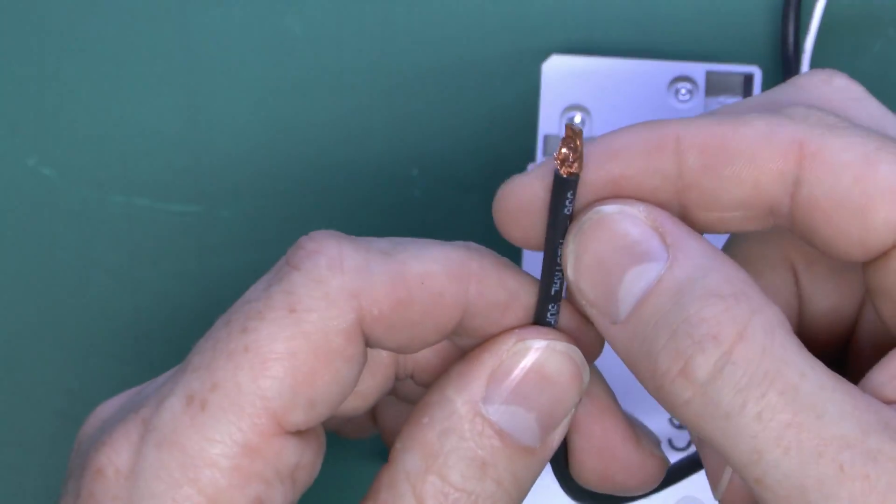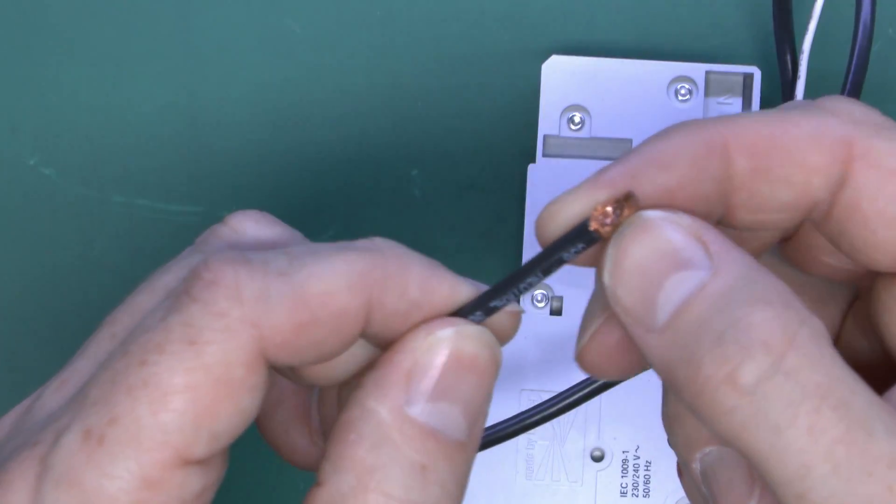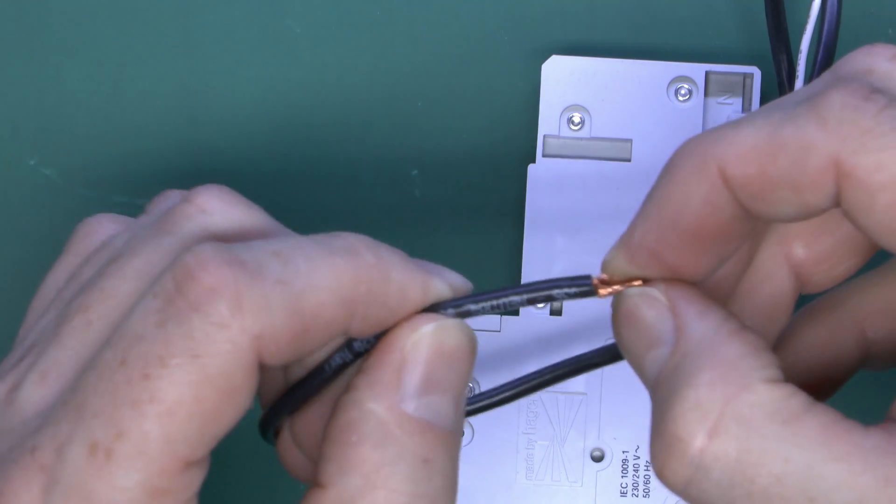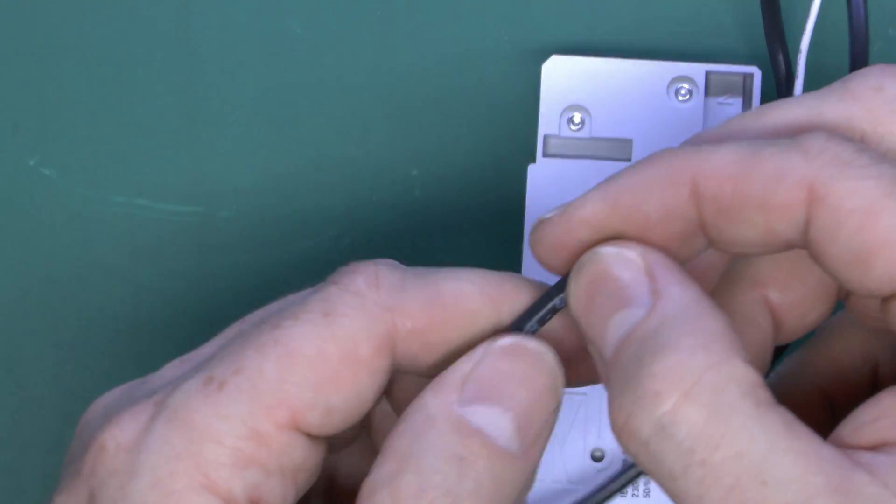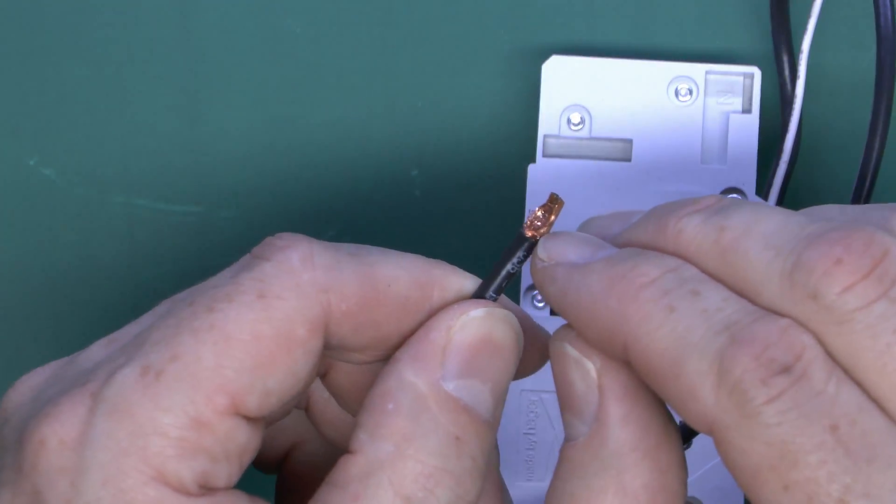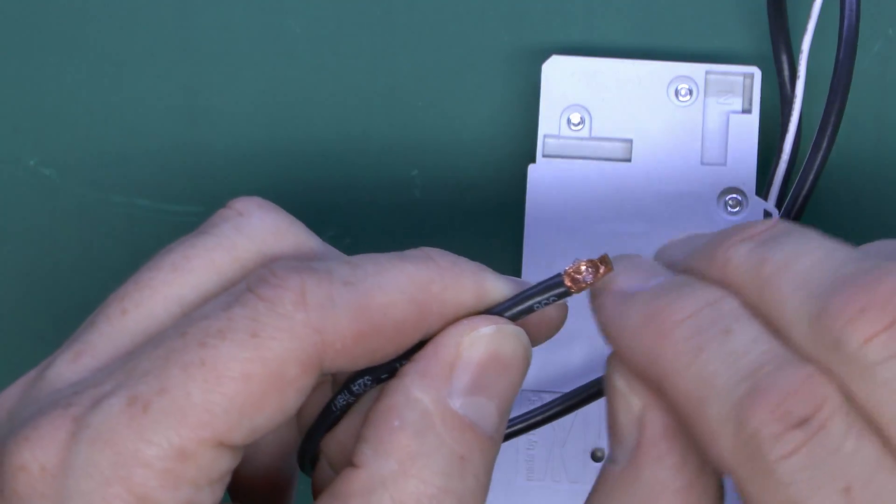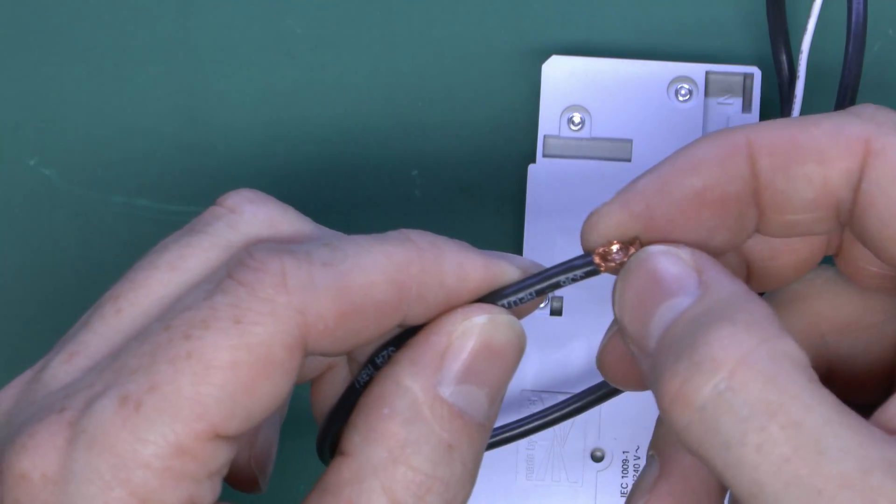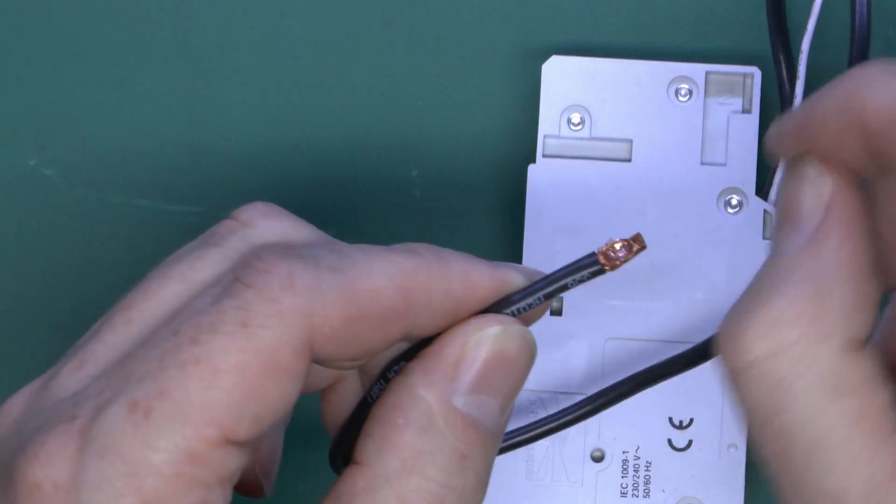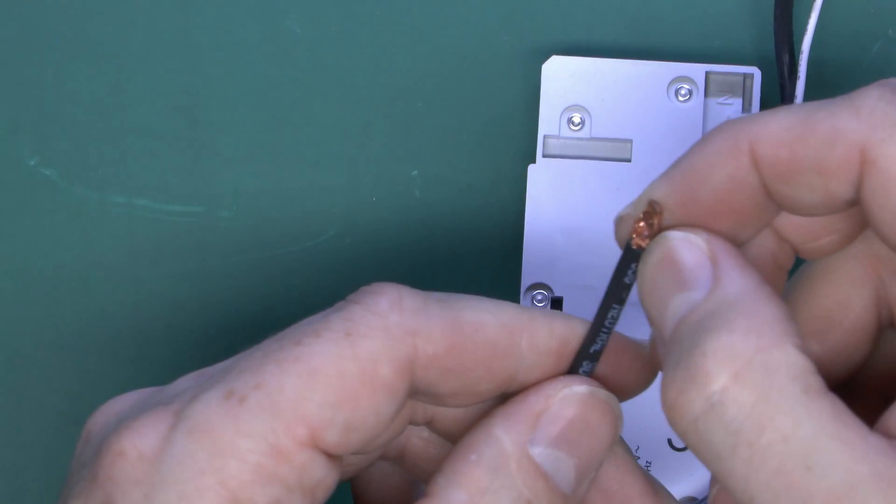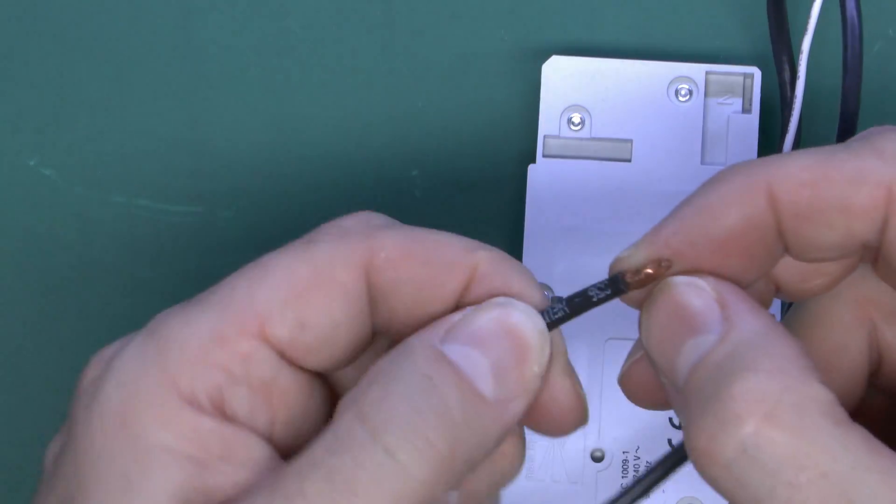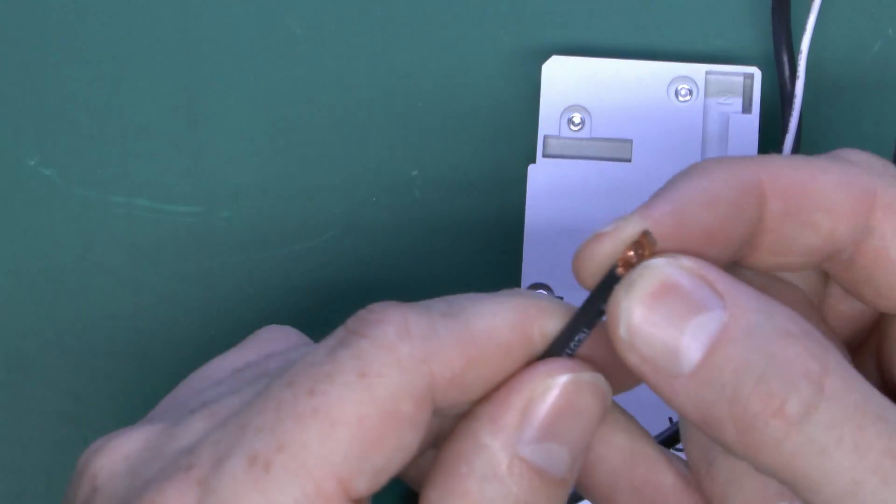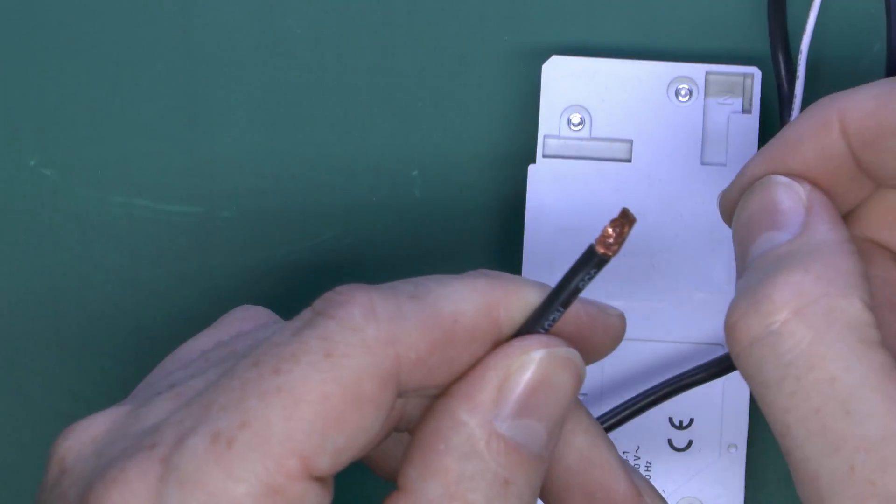Now have a look at the end of the wire for the neutral here. You see that it's actually been sort of welded or molded into a single solid piece. And this is done because the wires on these typically have a very large number of fine strands inside. So if it wasn't fixed together like this you'd have many dozens of strands all trying to fix under a single screw. That might not give a very good connection. So hence the manufacturer obviously welds this together in some fashion, so it's essentially just one conductor that you're tightening the screw down onto.